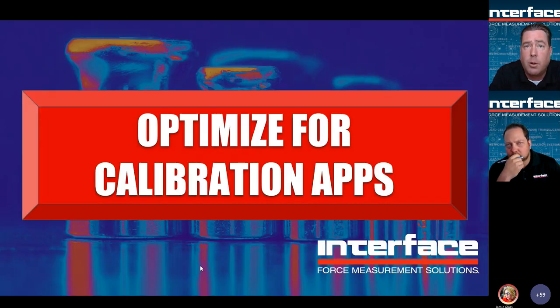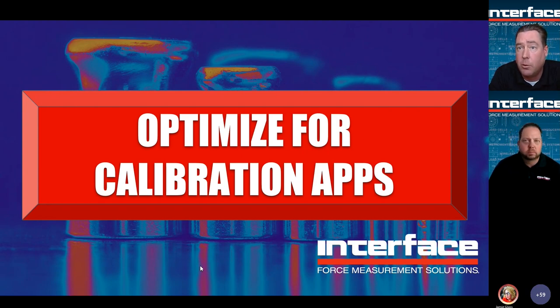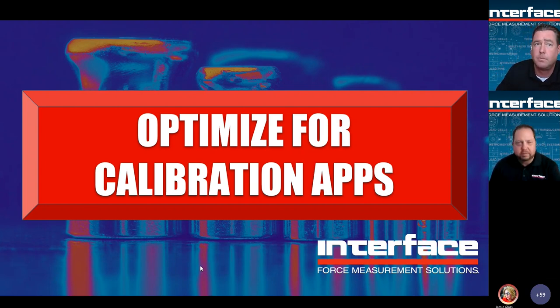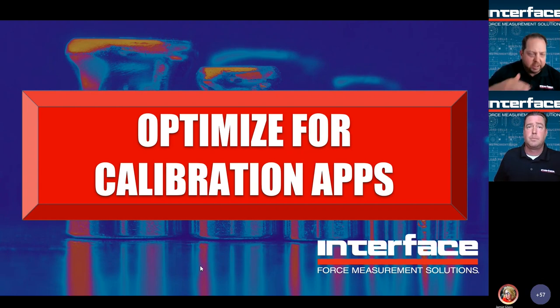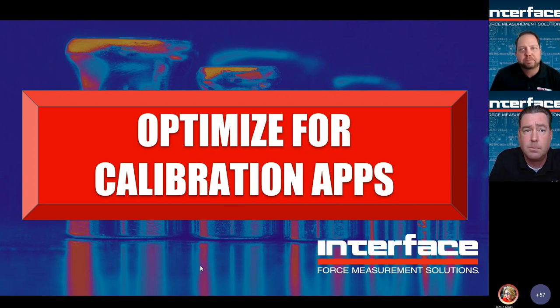Marcus, good question on the problem without the spherical tip. If you have a difference in parallelism between those two surfaces, you could have a moment load imparted, and it also can help with any misalignment in the actual load, or the concentricity of the applied load, I should say, as well. Again, just looking for that single point of contact between those two surfaces. Yeah, as that load cell deflected, of course, it would start to exist at an angle, and that would likely introduce significant error in that.